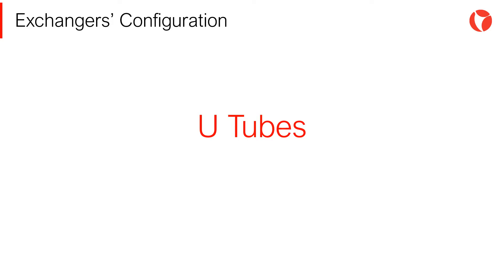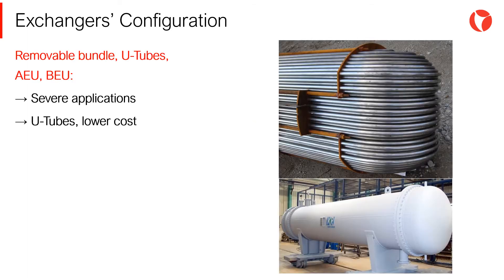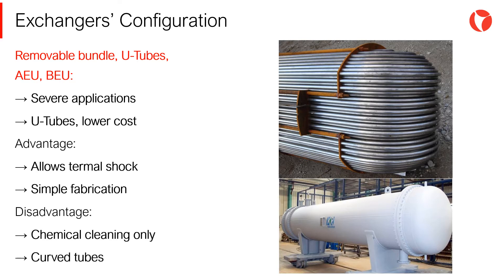The U-tube exchangers only have one tube sheet that supports and anchors all the tubes. This type absorbs thermal expansion at low cost. The main advantages are that they allow thermal shock, in other words, differential thermal gradients between the bundle and the shell. The fabrication of this type is very simple. On the disadvantages, only chemical cleaning can be performed inside the tubes with limited mechanical procedures, and the tubes must be curved, adding extra cost to the manufacturing process.